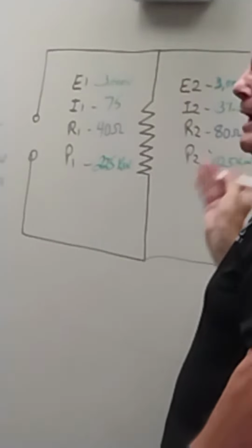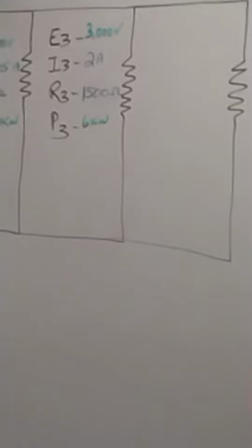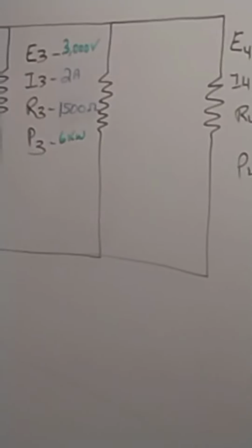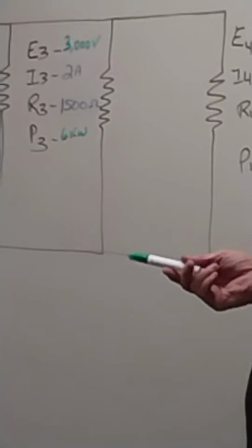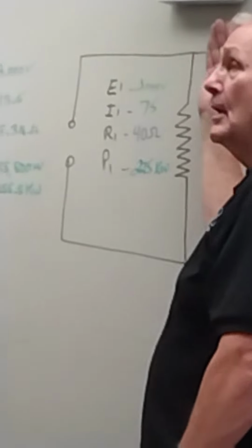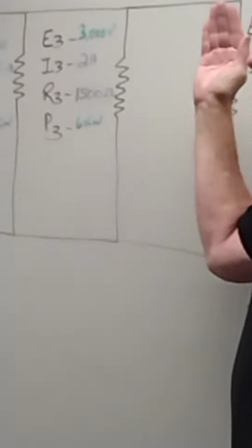It doesn't work because these wires have to carry all the current. It's only got the one path coming around, I'm leaving on one path from the power supply, I'm returning on one path. So therefore, it's gotta carry the current for all loads in the circuit. Now, if I only have one load up here, then the wire only has to be big enough to carry 75 amps. But because I'm adding all these other loads on, I'm adding current to the size of my wire, and that's what we gotta do. We've gotta size the wire for 118.5 amps.